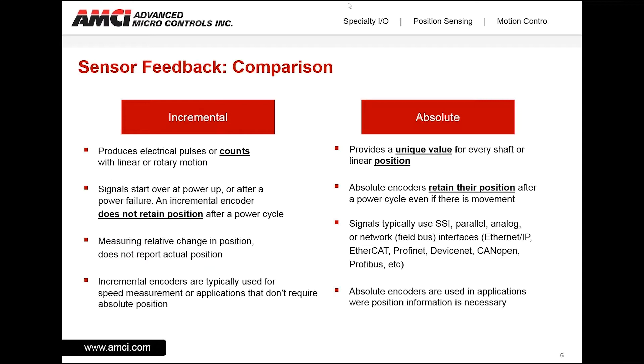For rotary sensors and position feedback in general, there are two types of outputs: incremental and absolute. Incremental sensors produce electrical pulses or counts with linear or rotary motion — think of a square wave. The signals start over at power up or after a power failure. An incremental encoder does not retain position after a power cycle, nor can it report back that the position has changed while power was off. It measures relative change of position and does not report actual position. Incremental encoders are typically used for speed measurement or applications that do not require absolute position.